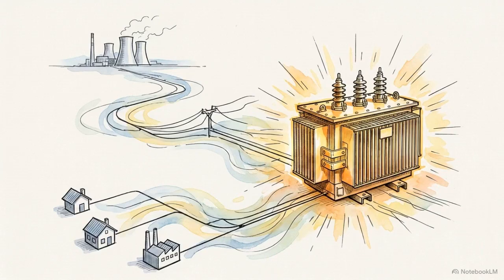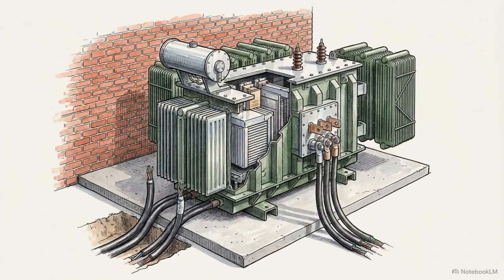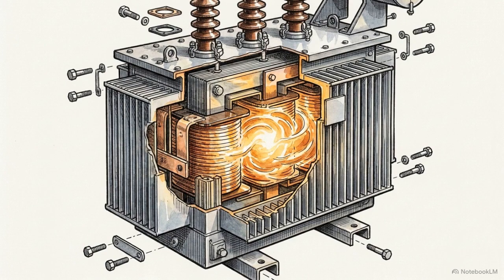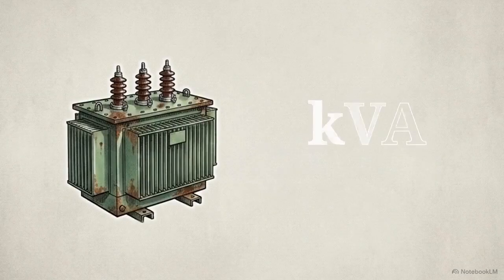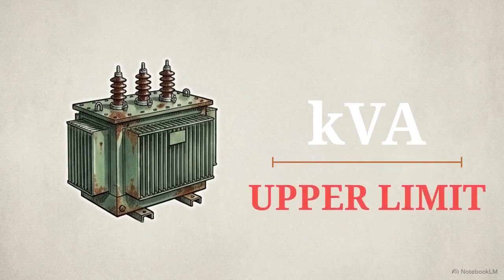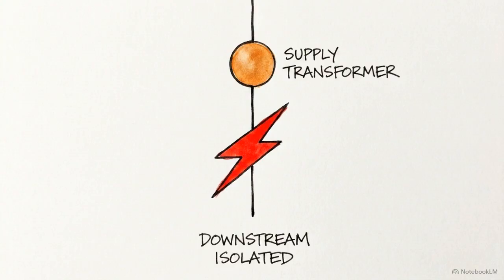To build an accurate mathematical model of a fault, we have to start at the absolute physical ceiling of the system, the grid's supply transformer. The total energy released during a short circuit is capped by this hardware. The transformer's physical size, measured in kilovolt amperes, dictates the maximum theoretical damage it can inflict. Looking at this standard engineering table, we can see the direct correlation between the physical size of the unit and its short circuit output. If we isolate a common industrial installation, a 500 kVA pad mount transformer, we see it generates a 12.5 megavolt ampere short circuit output. That baseline metric tells us the maximum potential energy available before any downstream wiring is even factored into the equation.